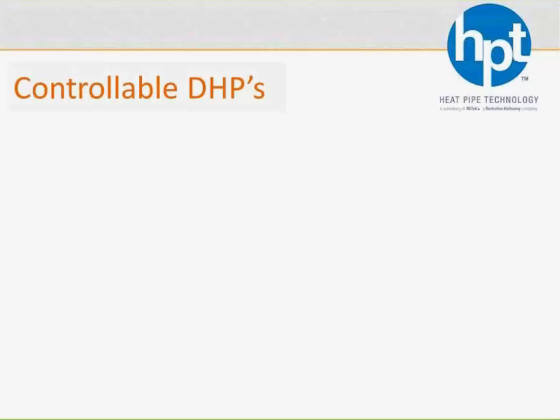So in many cases, the DOAS system is providing neutral air, or let's just say that the supply air temperature can float because you have some downstream terminal units handling the sensible load. But there are many cases where that temperature does matter. And if there's a downside to the wraparound heat pipe, it's that it's all driven on delta T. So the warmer the air coming in, the more heat we're going to recover, the more pre-cooling we're going to do, which is great, but the more reheat we're going to provide as well, and that might not be so great. So how do you control the amount of reheat that's being done?